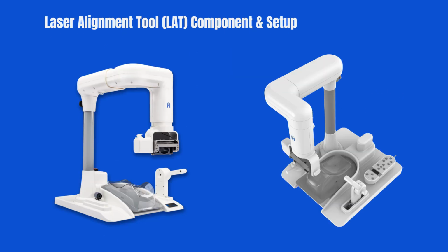In this section, we'll go over the components of the Laser Alignment Tool, or LAT, and how to set it up. The robotic scanning arm enables precise, automated imaging. The probe holder secures the ultrasound probe for imaging. The hand controller lets you adjust system settings and scanning parameters with ease. The laser module ensures accurate positioning for every patient. And the head support base is designed for the headrest attachment, keeping the patient stable.